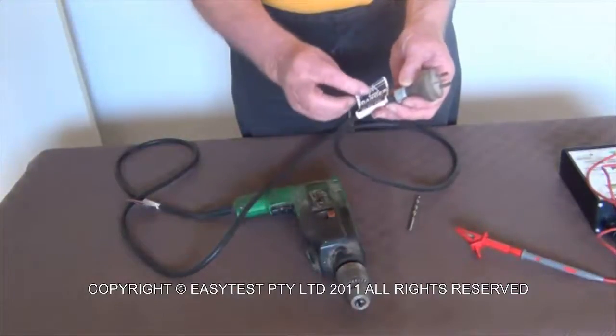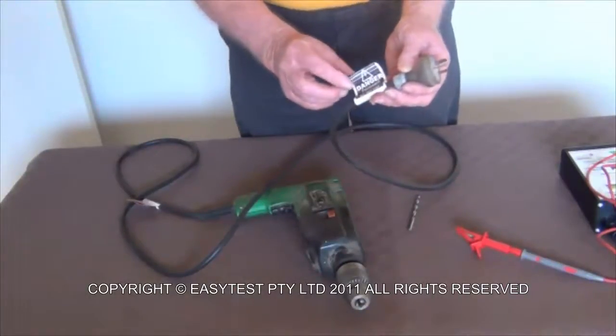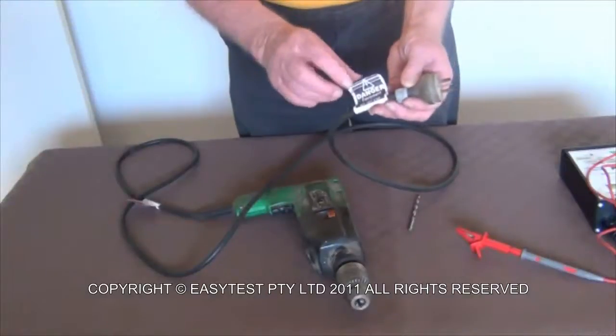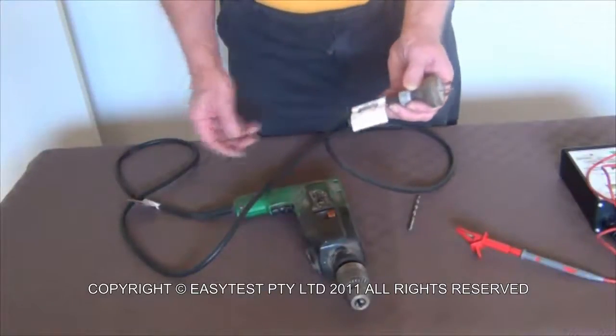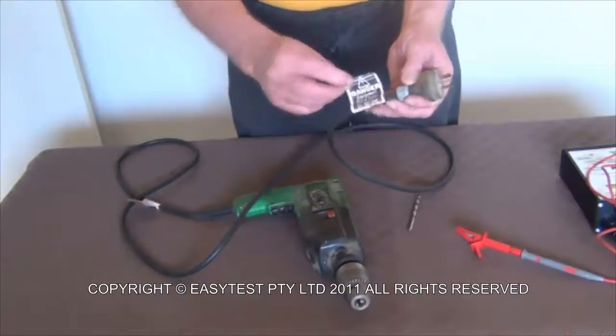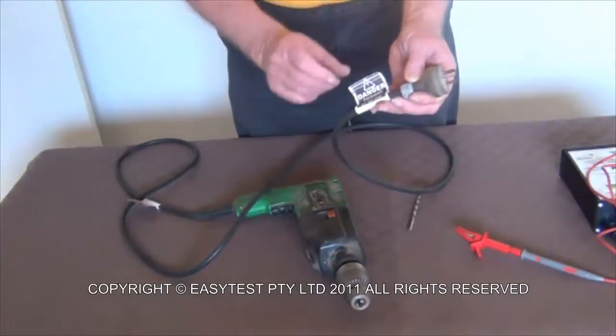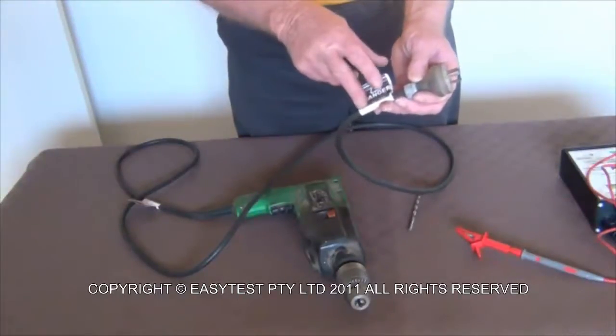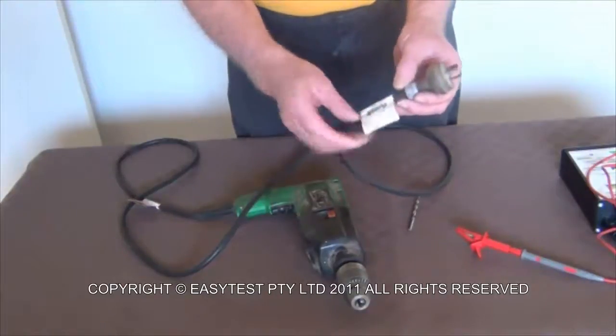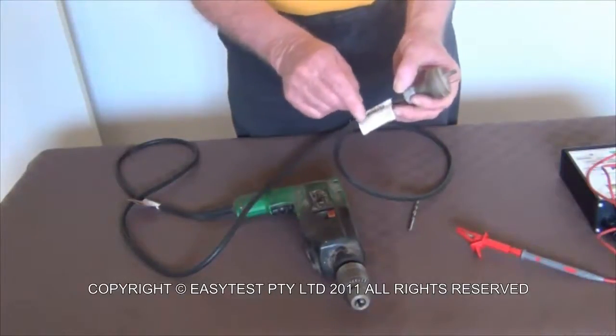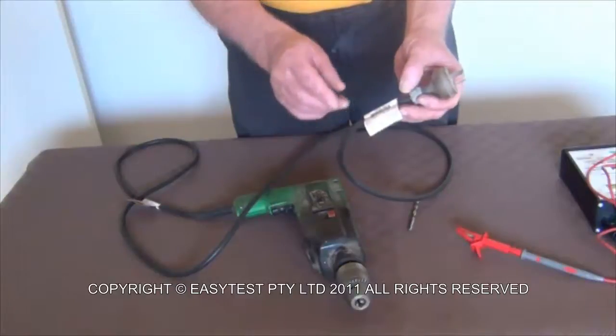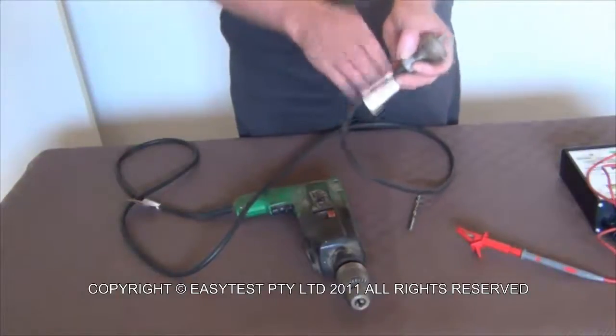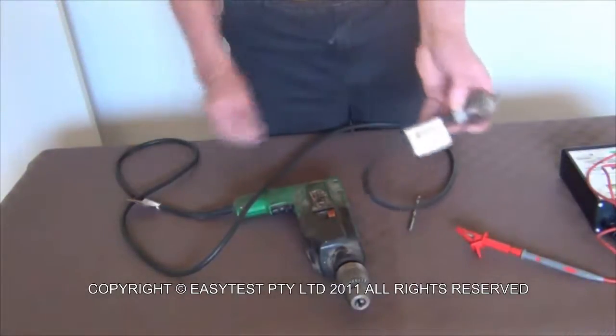Now these are one of the tags that are printed off on a machine. They are identical in every way to the normal tag, except on one side they have danger written on them in the same colour as the other tags, and on the other side it doesn't have a retest date and it has fail. So unless you actually read the tag, you can't tell that it's a danger tag.